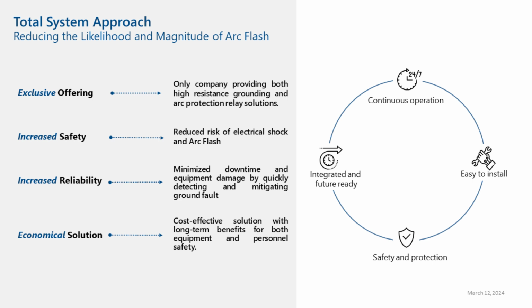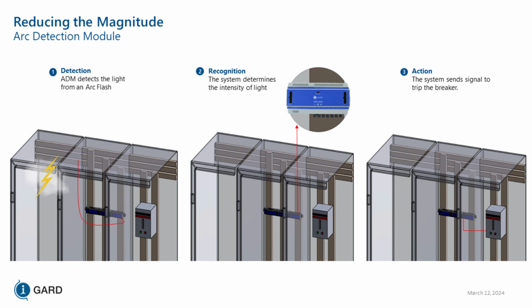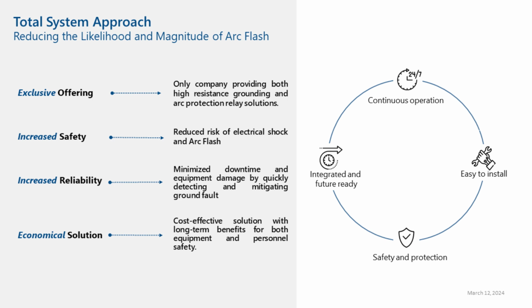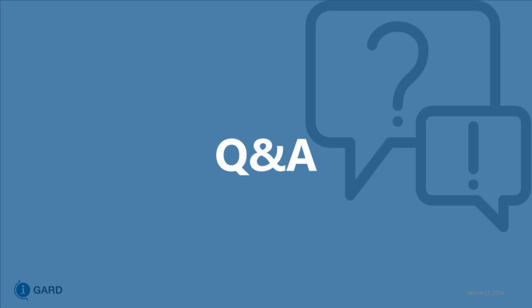So the total system approach, exclusive offering, only company that provides high resistance grounding and arc solutions. Increase safety, reduce the risk of electrical arc flash, increase reliability. And it's an economical solution. I've also heard from many people that they try to increase redundancy, but increasing redundancy does not increase reliability. So we're increasing reliability without adding more capital, and it's a more economical solution.